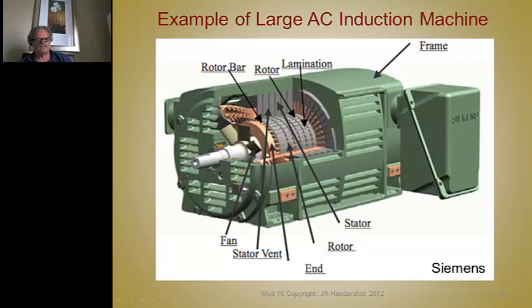We see here also a copper rotor, not an aluminum. You can tell by the color it's copper. And you see that the bars that go down the core pass through these cooling vents. And the bars extend past the core before they're attached to the end ring. The end ring is not right up against the core like it is in smaller die-cast aluminum machines. There's two very good reasons for that.